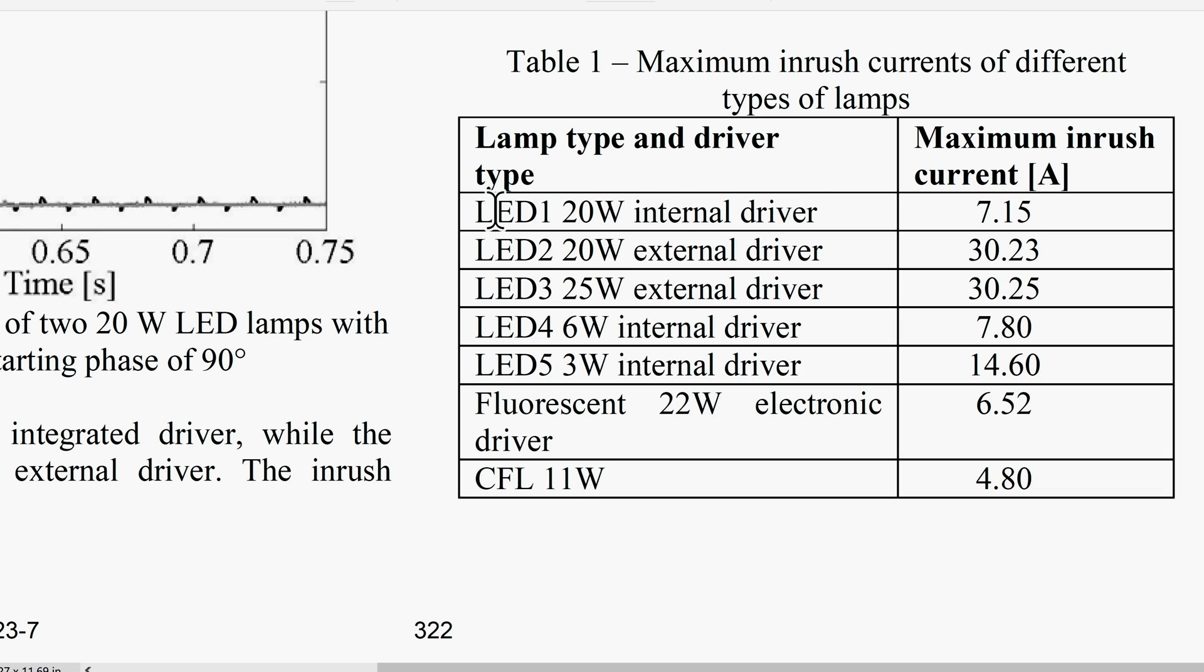And just having a look at some of the results. Their 20 watt LED with internal driver, the maximum inrush current they found was 7 amps. And then they had another LED using an external driver. And one can see that it's not uncommon to get these very high currents. This is 30 amps. And even here a 3 watt internal driver. That is a small LED light. And look at that maximum inrush current. 14 amps.